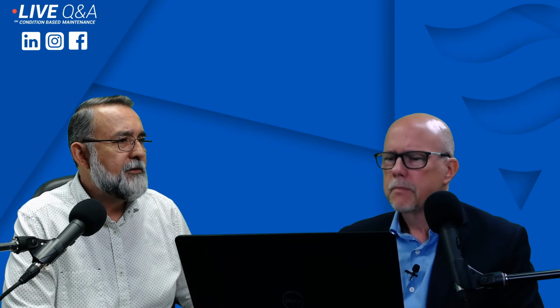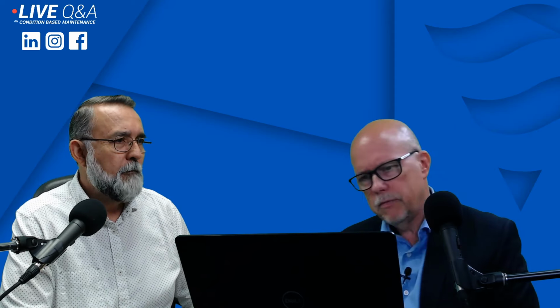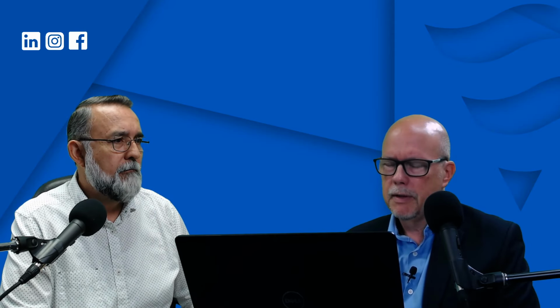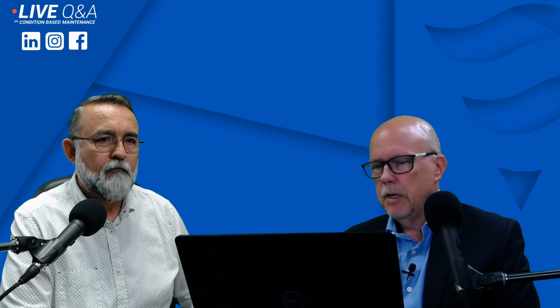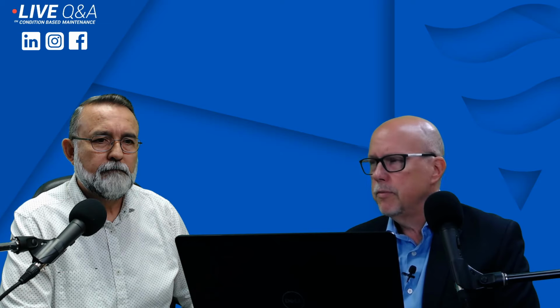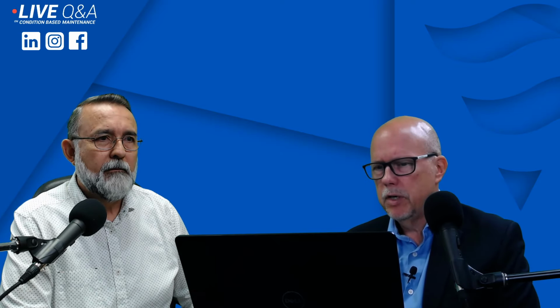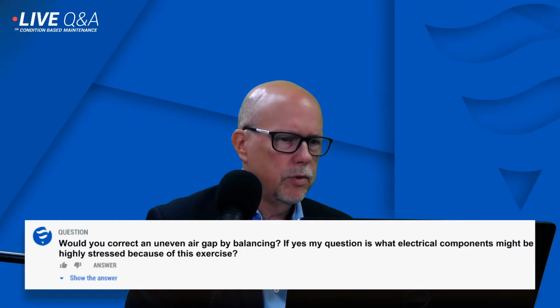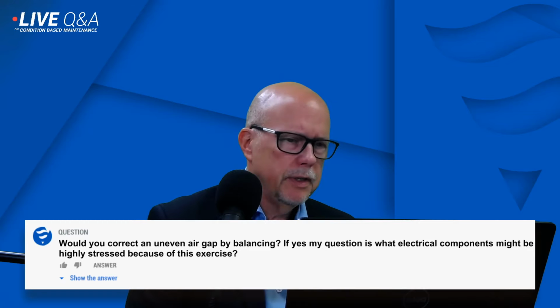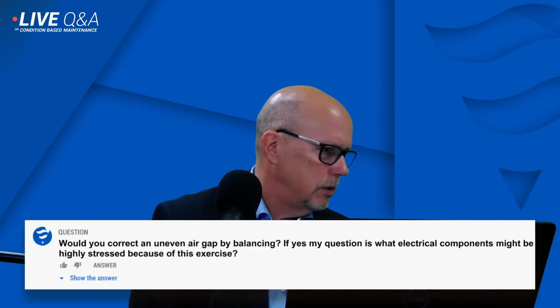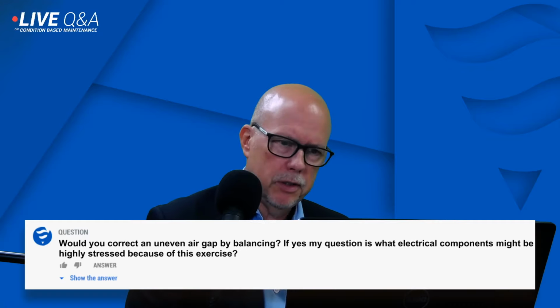Yes, Paul. Yes, we have an answer back. He says, yes, it's a vertical machine. It's a Francis turbine. It's a Francis unit, and the turbine vibration decreases as they apply the field. I'm going to ask another question again, sorry, but are the vibration levels at the other guide bearings near the rotor high or are they low? We'll wait for his answer back. Might be also interesting to find out when it decreases from what to what? Is it a significant decrease or just a slight decrease?